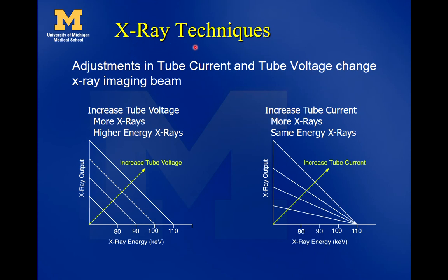This also helps explain x-ray techniques — the specific tube voltage put on an x-ray tube for imaging, as well as the milliamp-seconds or tube current going through it. In this graph, we're increasing the tube voltage while keeping all else equal — going from 80 to 90 to 100 to 110 kilovolts between cathode and anode. When we turn up the tube voltage, keeping everything else equal, we get more x-rays as we go to higher tube voltages.